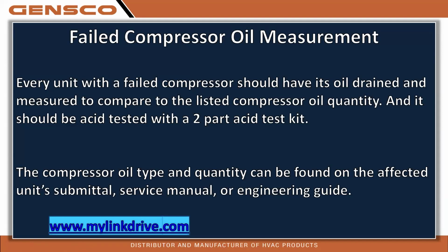happens. The proper procedure is to pull the compressor out and drill a hole in it if it's the dual rotary compressor, near the bottom corner edge. You can't tip it over and pour it out of the discharge line. It's not going to come out. It's not going to come out of the suction line. You have to drill a hole in the bottom of it. You have to catch it in something that you can measure, and you have to look at the quality of it. What does it look like?